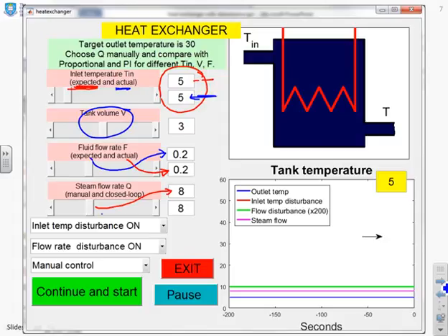The steam flow you can set manually and that value will go there. But the actual value if you're using closed loop control will be there and it will be slightly different. If you're open loop the manual value will be what you get. If you're closed loop then it will ignore the manual value and give you the closed loop value.